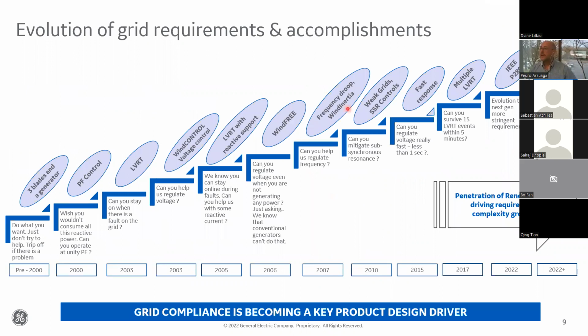This slide shows the evolution of grid requirements and the accomplishments we've had over the last 20 years or so. As I said at the beginning, before 2000 this was all an experiment - don't worry too much about it, if something happens in the grid you just disconnect, no worries. Then some utilities started saying, we wish you would consume this much reactive power, can you operate at unity power factor? But it was really in 2003 when grid requirements for renewables in general, for wind specifically, started changing dramatically.